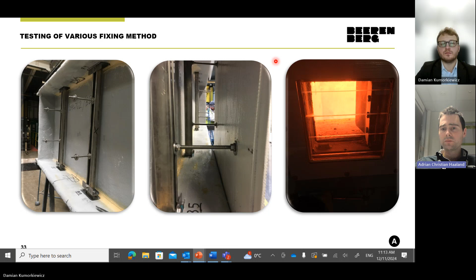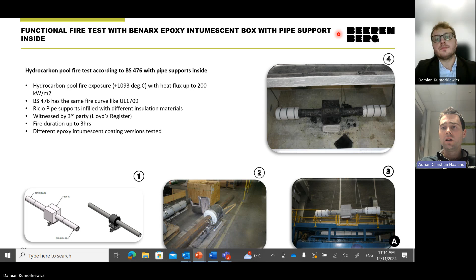Some curiosities here as well. We did some specialized tests for cryogenic supports to see how they would hold up. Cryogenic supports are made from various kinds of materials: PUR foam, aerogels, cellular glass, etc. And we did a series of tests to verify to what degree the supports will collapse, because some of these materials are not fireproof, and at what speed, with what heat ingress, and what extra insulation the insulated pipe supports provided in the test. The longest test there was up to 3 hours, and it gives an edge in terms of providing minimum thickness for the removable PFP to avoid doubling up, so to speak, on the thickness schemes.